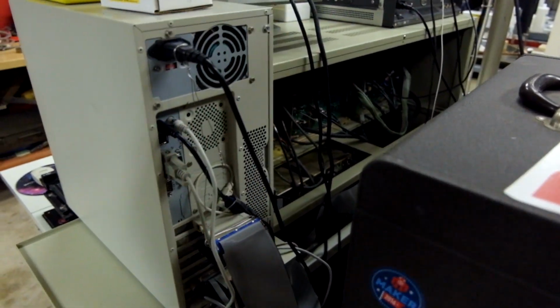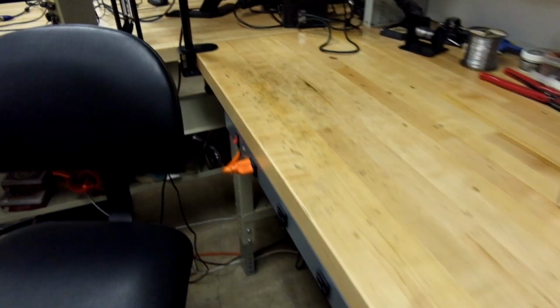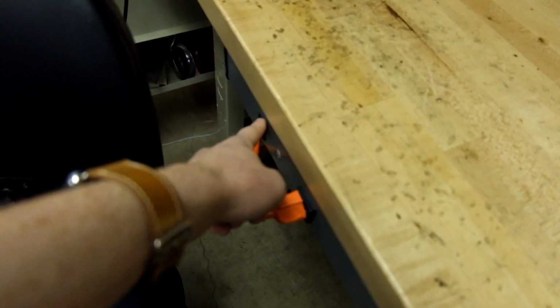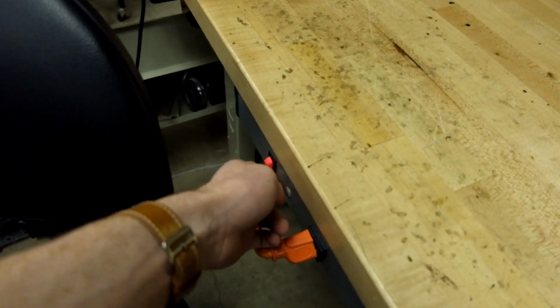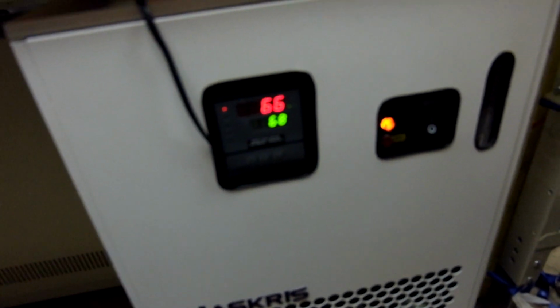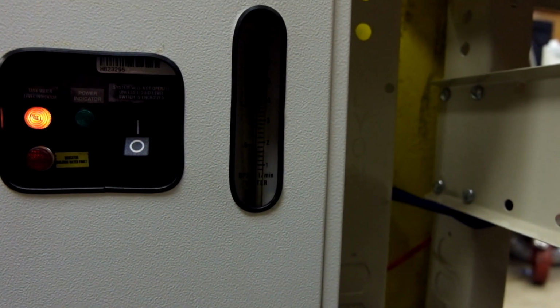It's going to get a little bit noisy. The chiller runs water through the diffusion pumps, and also in the back of this console here there's a bunch of electronics that are water cooled. So this is an interlock switch for the chiller. Now that's on. I want 68 degree water, which is about 20 degrees C. Right now we're at 66 degrees, so that's going to come up. And we can see over here that we're at 5 liters per minute, just like I want.